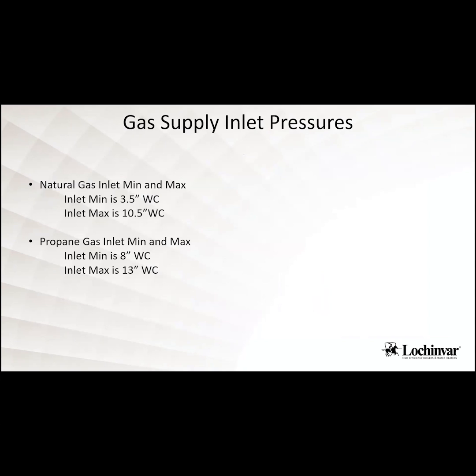All right. Well, then we'll jump into the gas supplies. So the natural gas minimum inlet is 3.5, and the inlet maximum is 10.5. Sorry, propane I misquoted before. Propane's minimum is 8 inches of water column, and inlet max is 13 inches of water column.